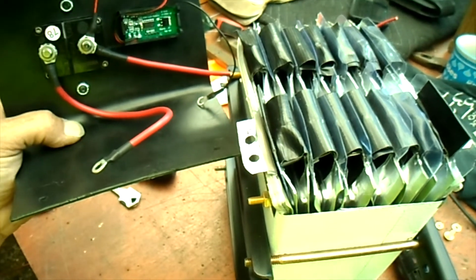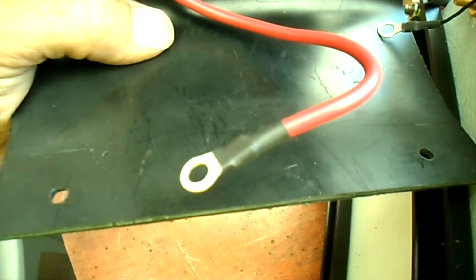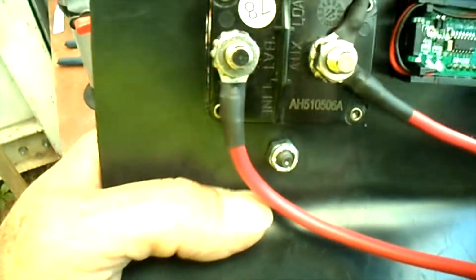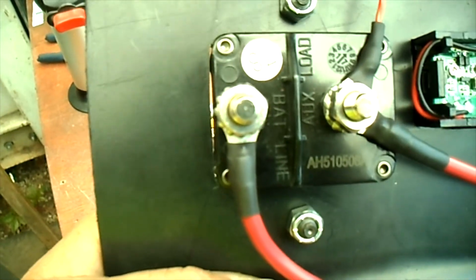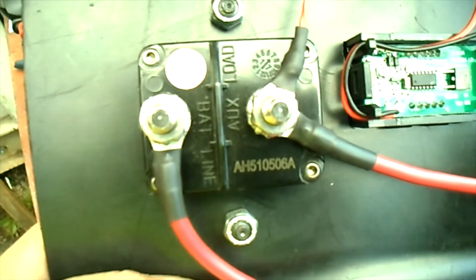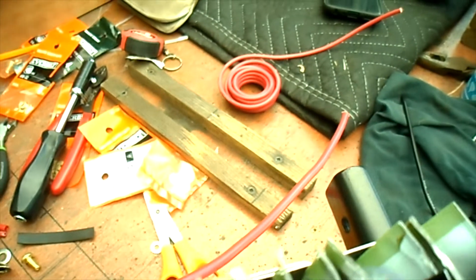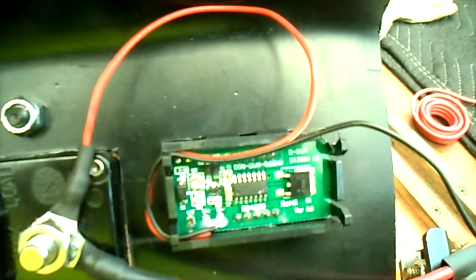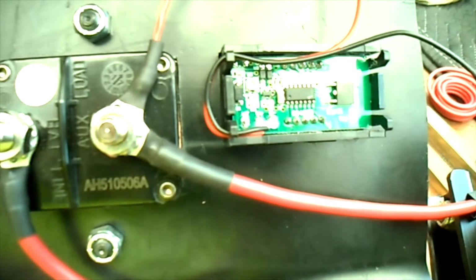Getting our battery top wired up here. Our positive terminal right here will connect to the red wire, which goes to the battery line side of our circuit breaker, and then the auxiliary or load side will exit. Also our meter, I've got the positive hooked up to the auxiliary load side, so the meter will only come on when the circuit breaker is on, so it won't be a constant draw. Then our negative will hook to our negative terminal here, and I've got our negative wire that will exit.